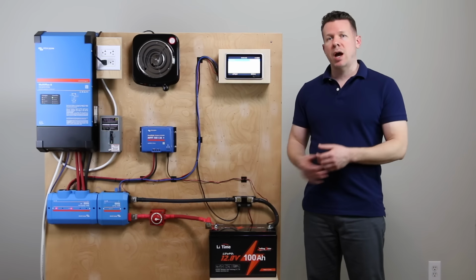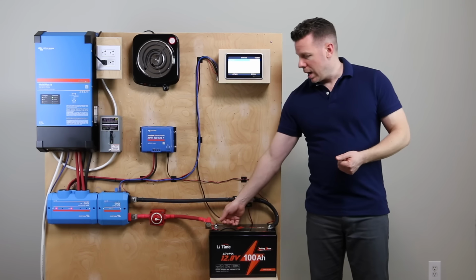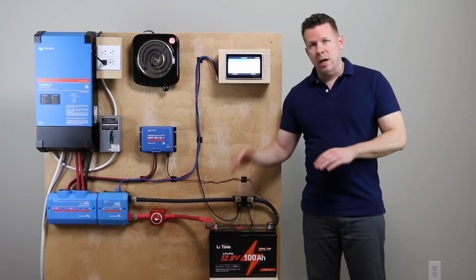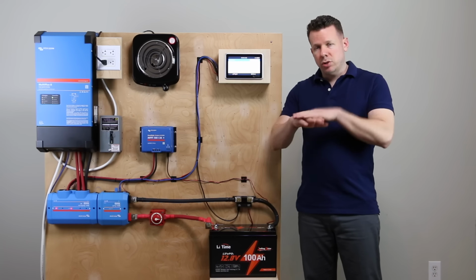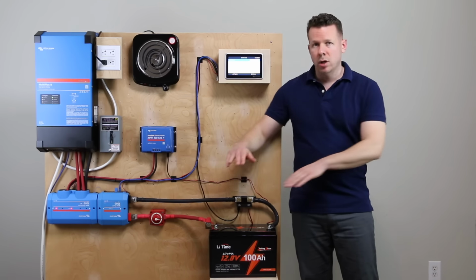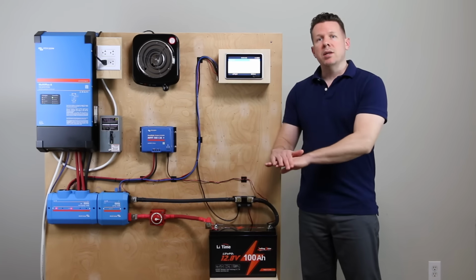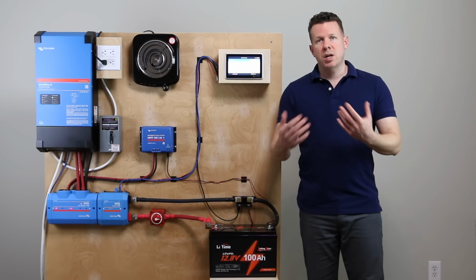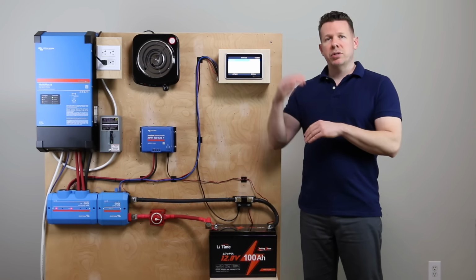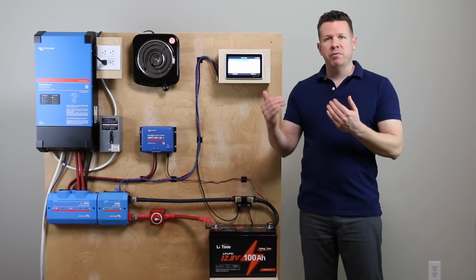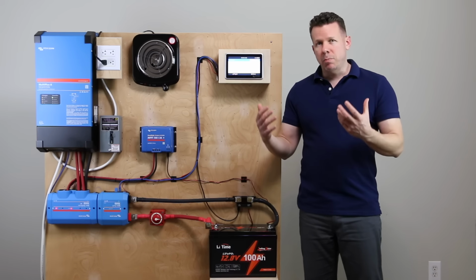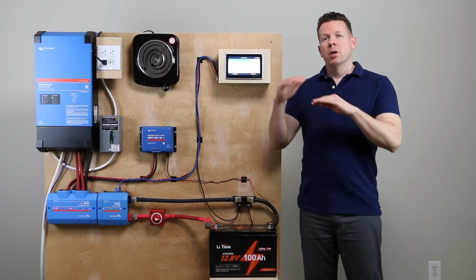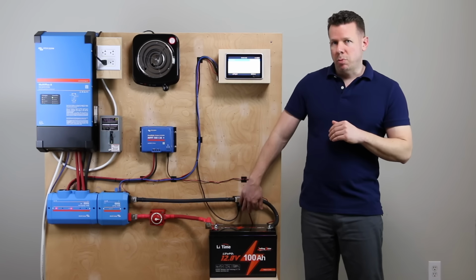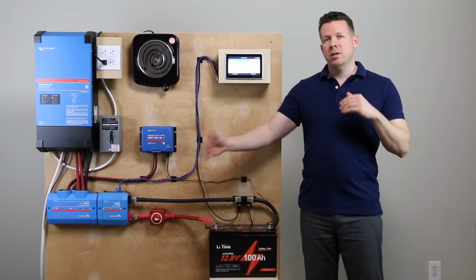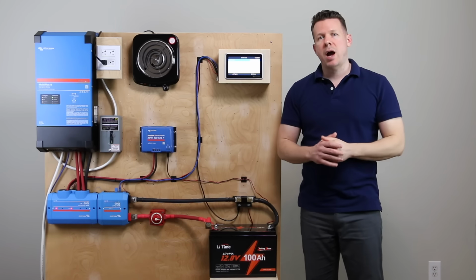Now that changed. I used a butane torch and heated up the battery terminal, with both temperature sensors from the SmartShunt and the Lynx Shunt on the same terminal. I heated that up and looked at their readout, and at some point when it got up to 115, 120 degrees, the temperatures where it really matters, the SmartShunt did pass the Lynx Shunt at those higher temperatures.